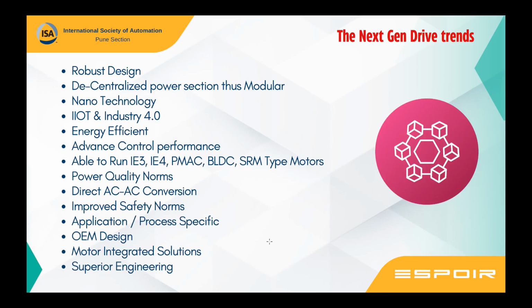In 40, 50 years, there is no change in the motor. AC induction motors came into the picture in the 40s, 50s. Even now, the same induction motors are being used. It has just become more energy efficient by introducing IE2, IE3, IE4. But in terms of design or construction, it is still the same. So now the other technologies are parallelly coming, a PMAC, BLDC, SRM, SYRM type of motor. Now your VFD should be able to drive these motors. So it is a control feature, algorithms. So your motors are changing, the drive is also constantly changing. The modern drives are able to run without any change.